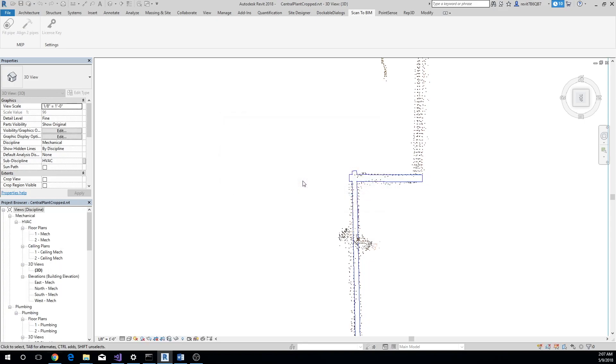Earlier, we mentioned the pop-up asking whether you want to make the angle between the two pipes exactly 90 degrees. This is required in some cases because Revit may not add an elbow if the angle is very close to, but not exactly, 90 degrees. In such cases, you may want to align the second pipe so that the angle is exactly 90 degrees.